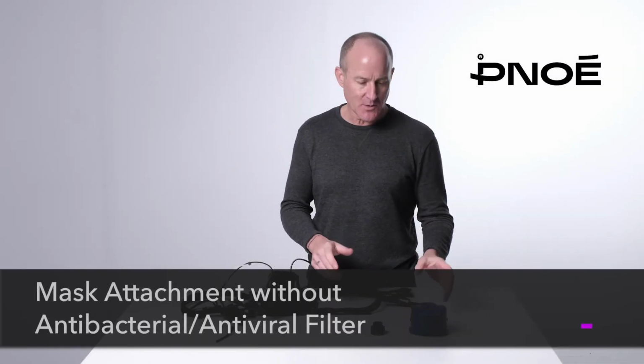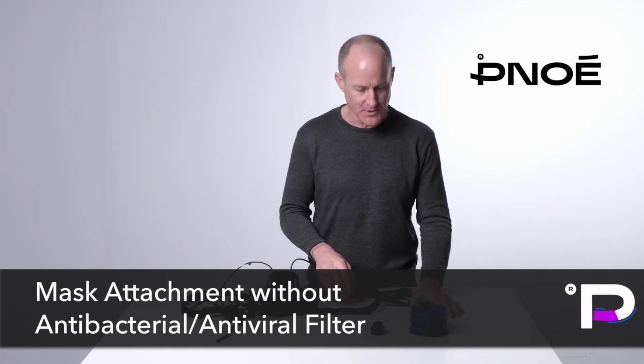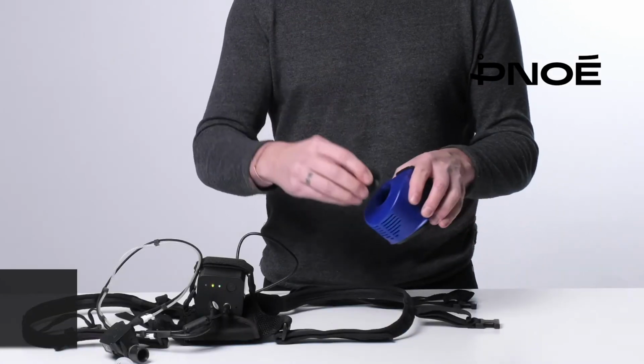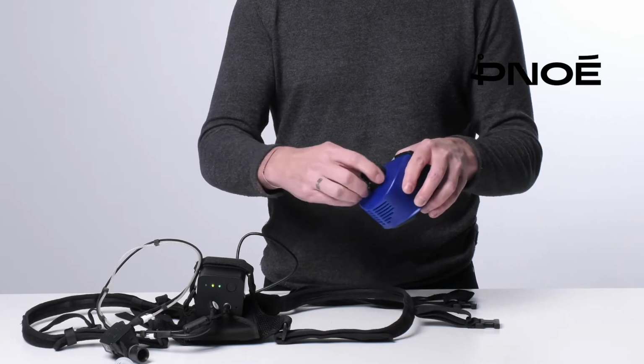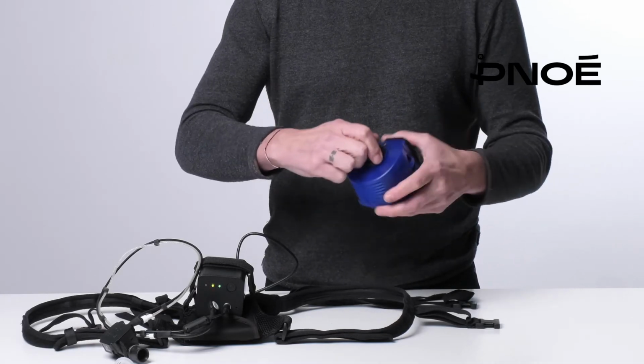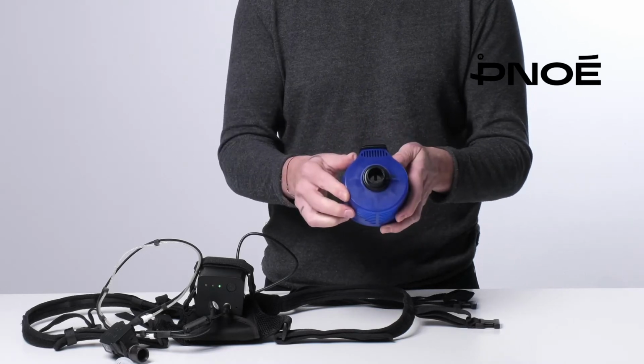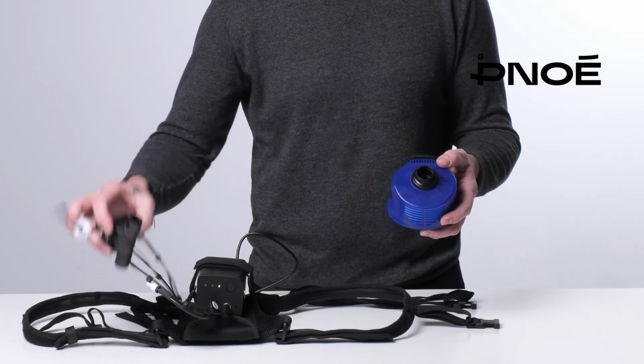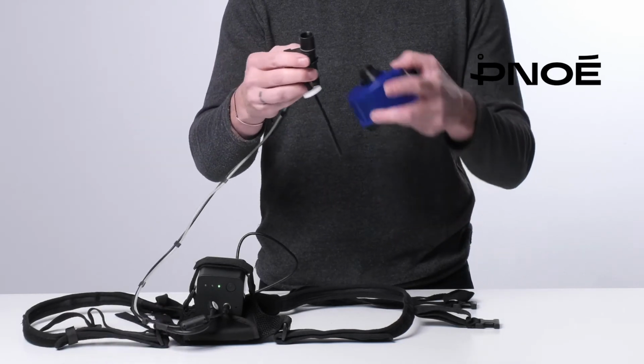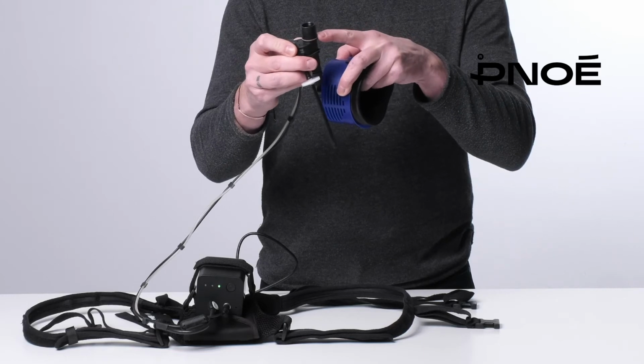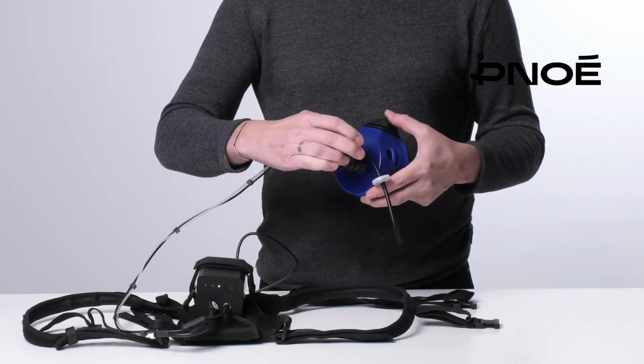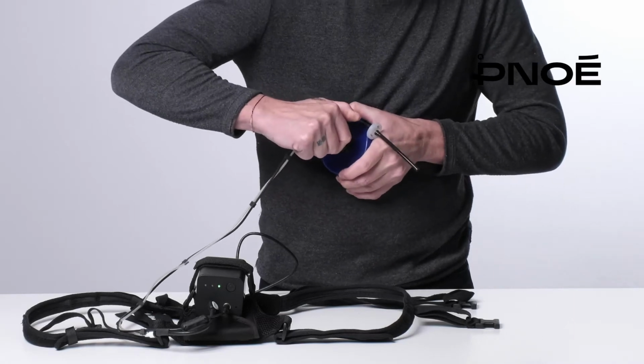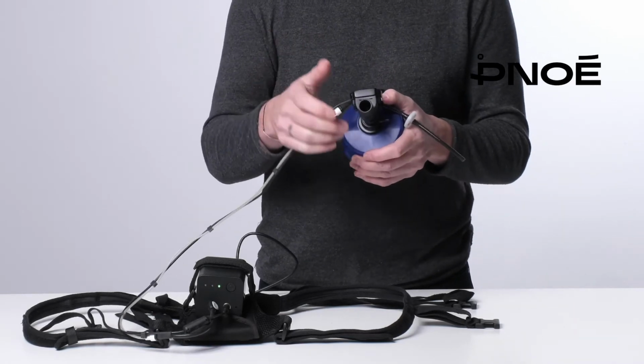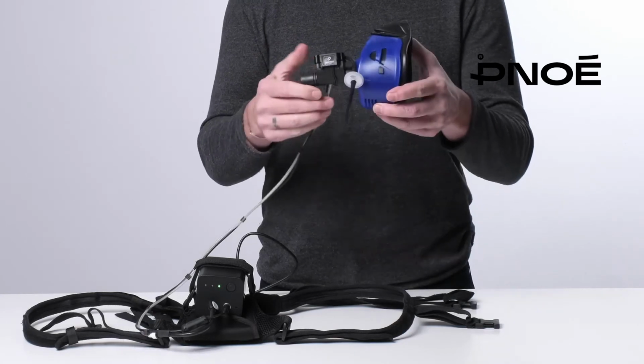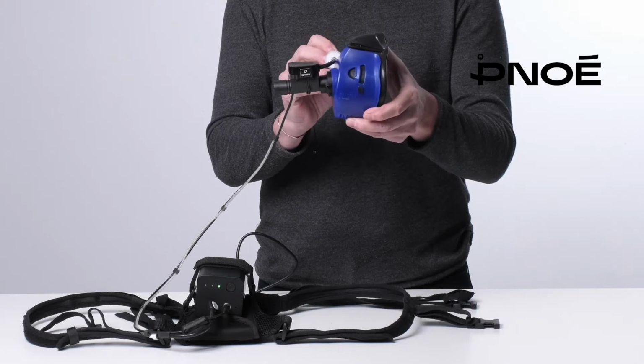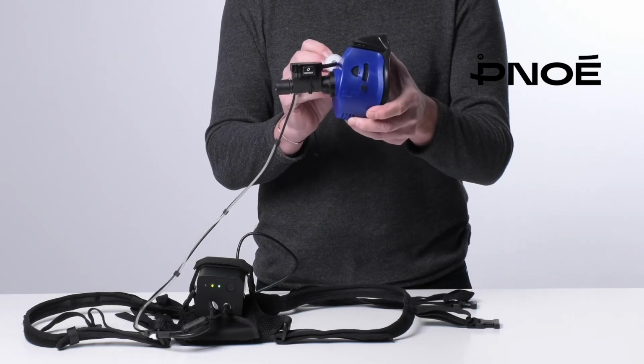When completing a test without using an antibacterial antiviral filter, you take your mount with the screw adapter and screw it in all the way until you get it nice and tight and it's very stable and secure. Then you take your flow sensor, ensuring that you're inserting the end with the rubber ring to create the seal. You're going to push it in and you'll know it's well seated. You'll feel a nice solid click. And that is the proper setup for a mask without an antibacterial antiviral filter.